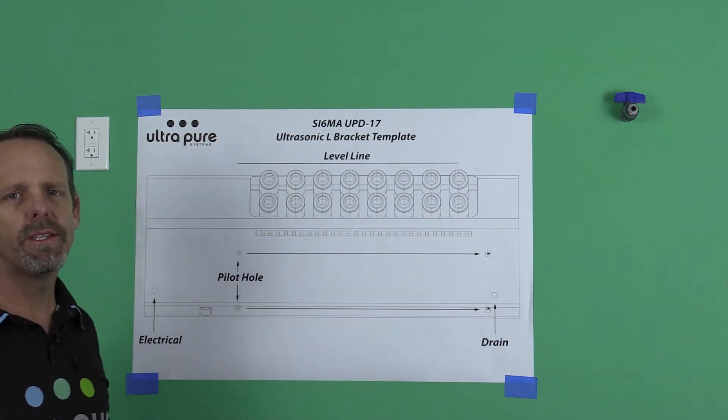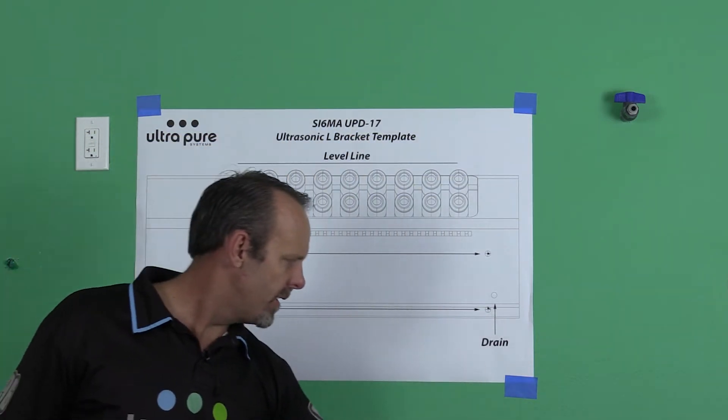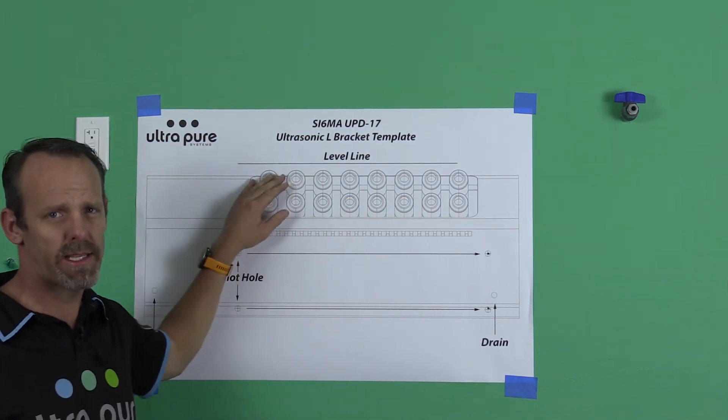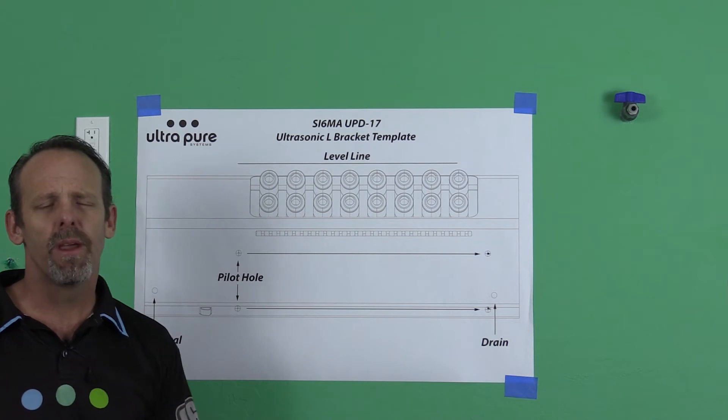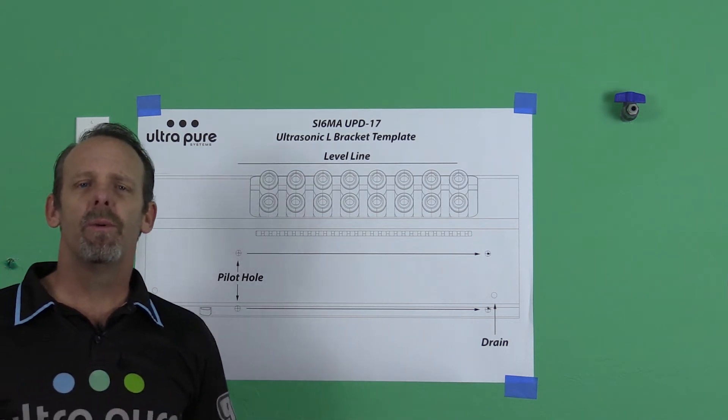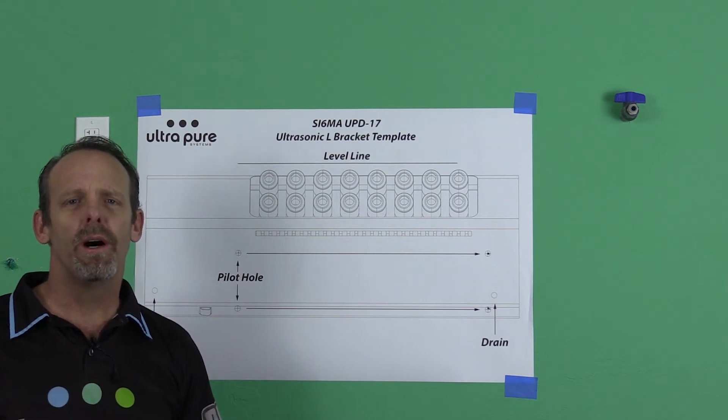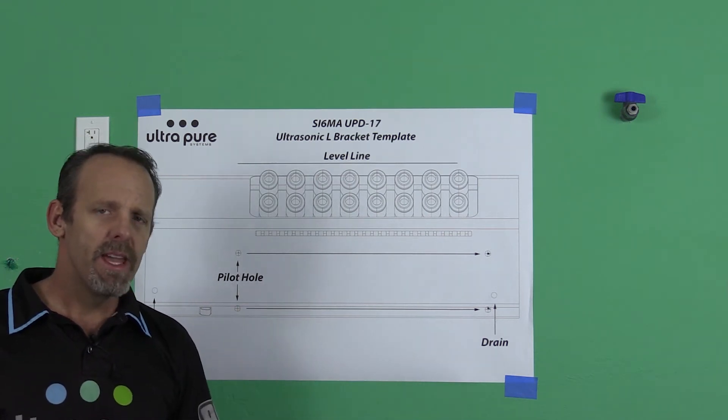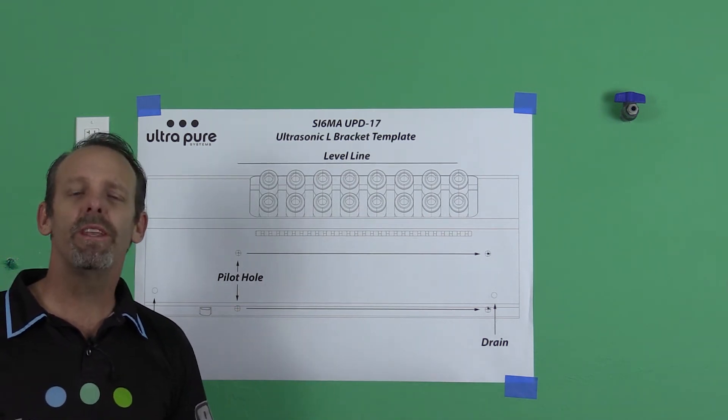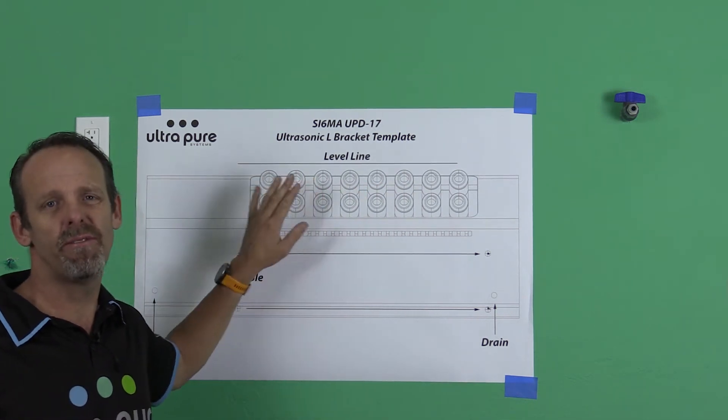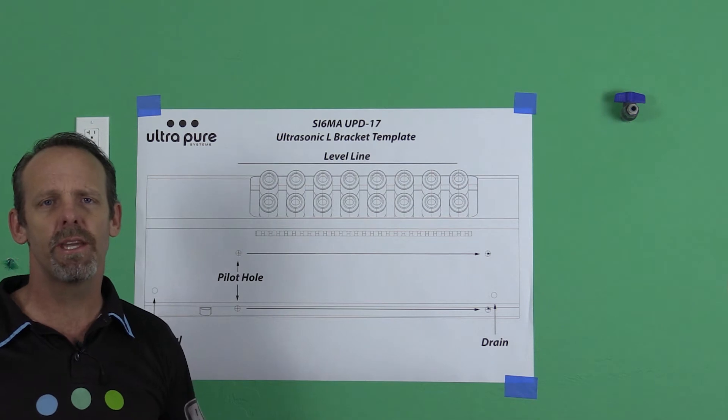You're going to want to make sure where it says level line that we are in fact level. And what that's going to do is confirm to you that the humidifier, once it sets onto the L brackets, is going to be level. If not, what's going to happen is the very small water bed that is below in the humidifier, if it's not level, it's going to affect the operation of the mist that comes out of all these nozzles. So it's a very important part of installation to make sure.